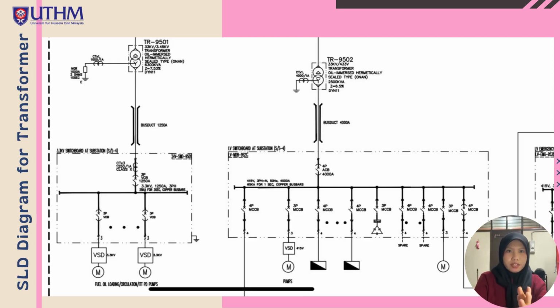We managed to get the SLD for all the transformer, and this is the single line diagram for TR9501. It shows how the transformer is integrated into the ATB electrical system. You can see the 33 kilovolt incoming supply enter the transformer, and then the power is distributed through the bus duct, ACB and bus bar system. This SLD demonstrates the complete power path from the utility supply to the final motor driven pumping system for this transformer TR9501.